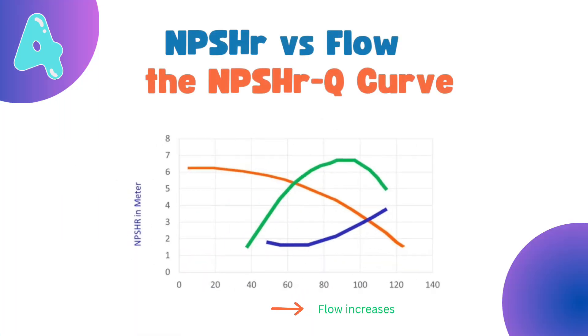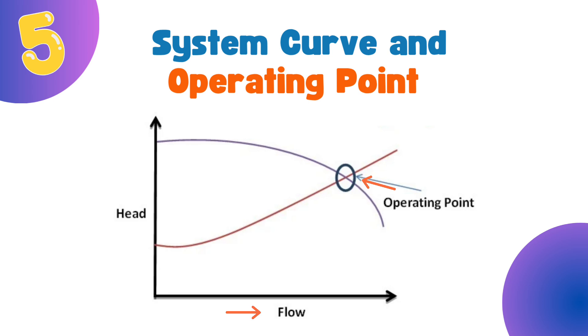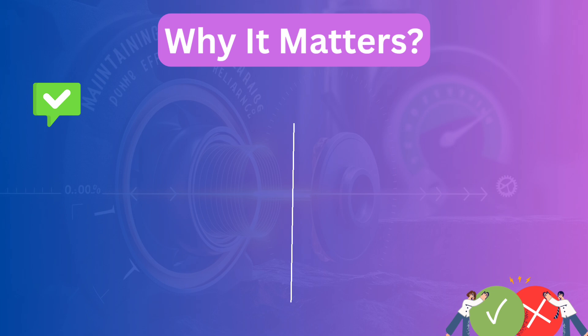Fourth, NPSHR vs. flow rate, the NPSHRQ curve. Net positive suction head required increases with flow rate. To avoid cavitation, the available NPSH must always be greater than the required. Fifth, system curve and operating point. When the pump curve intersects with the system curve, which represents piping and load, that's the operating point where your system will actually run.